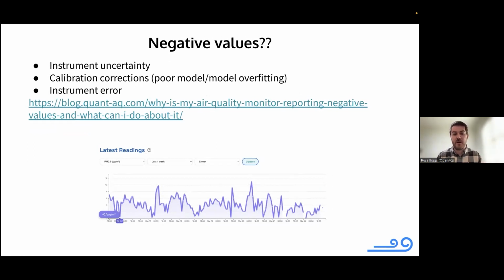A lot of this will come from corrections based on calibration. The model could be overfit and could be dragging the number down. Sometimes instruments simply have errors that allow them to go into negative values. You can see in the chart here, we have a negative 0.1 micrograms per cubic meter for PM 2.5. This could very possibly be overcorrection, driving this value negative.